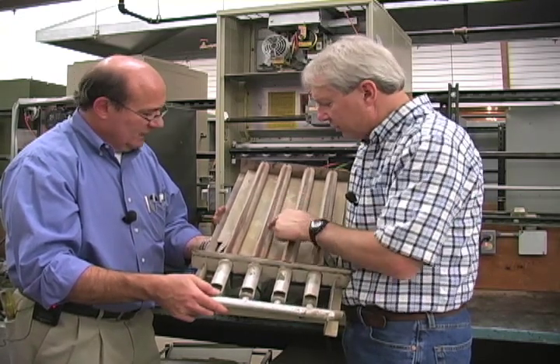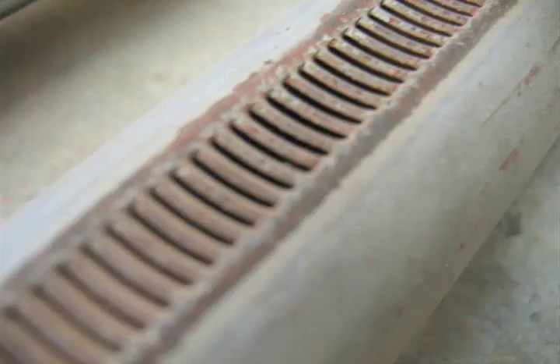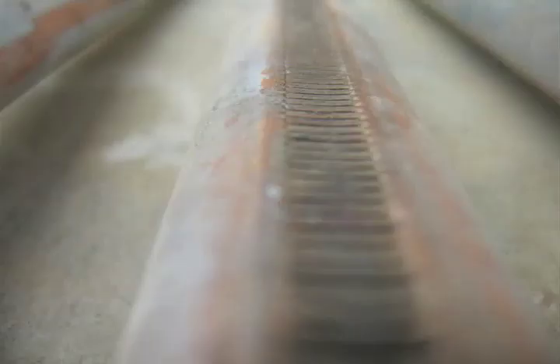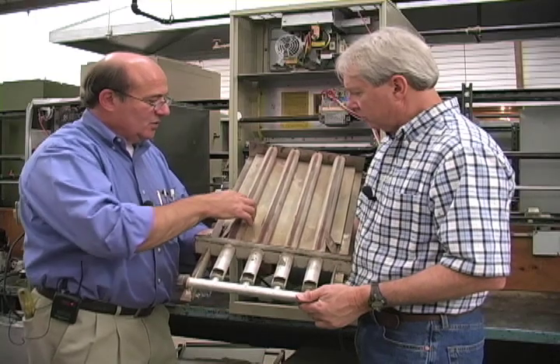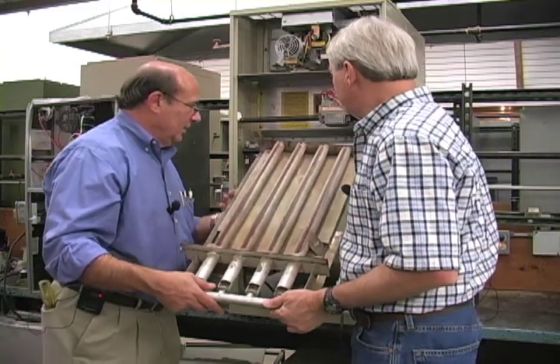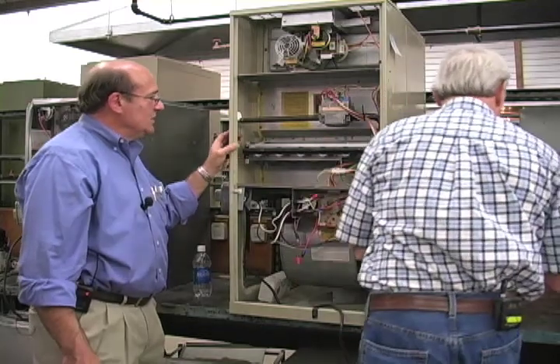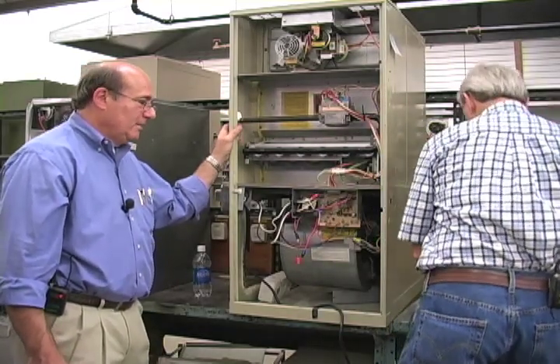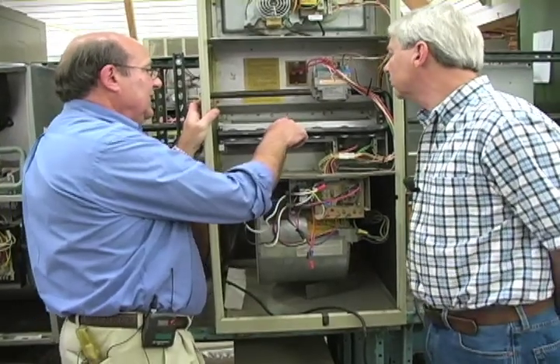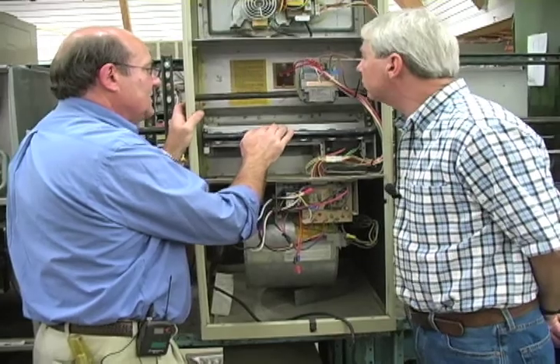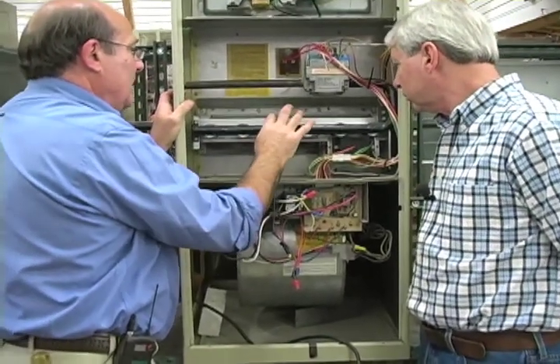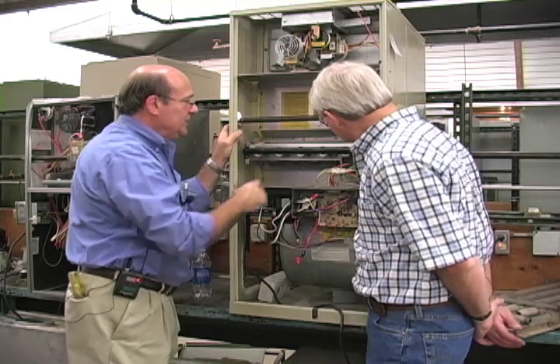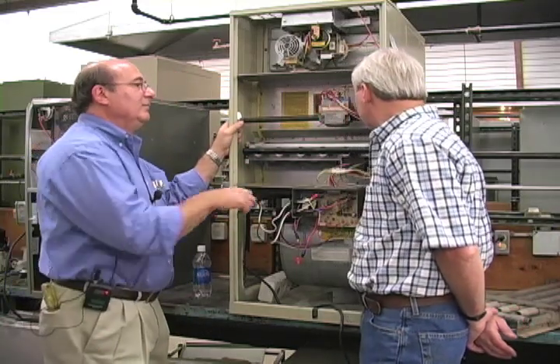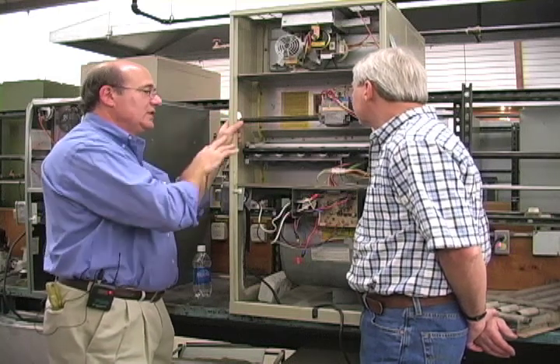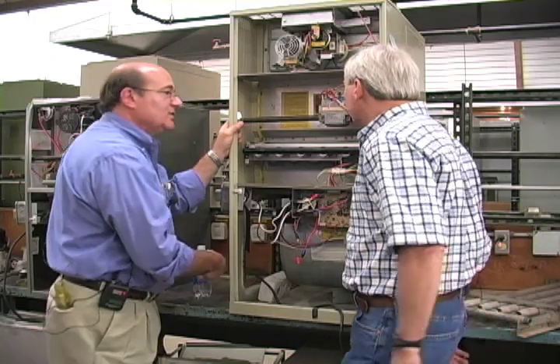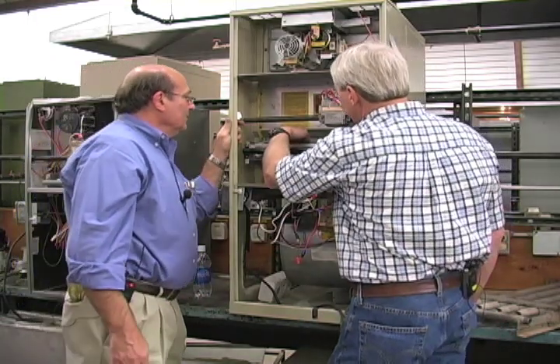These are actually perforations. That's correct. The little slots in the top of that steel tube, and that's what allows our flame to come out. And then the flame, of course, rises up through the heat exchanger. This newer furnace, we can set that down. This newer furnace has a different style of burner. It's called an in-shot burner. And basically what it does, it injects gas at the inlet port over here, blows it through this nozzle, and then the nozzle blows the gas with the primary air that's coming out through here into the heat exchanger, and carries it up through a series of tubes inside there, and then we blow our air across the outside of those tubes. Why the gap between the initial tube and the burner tube?